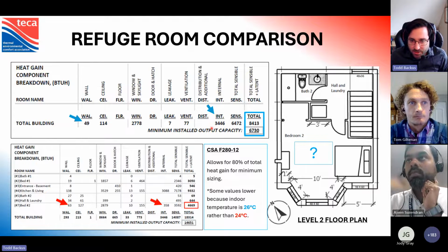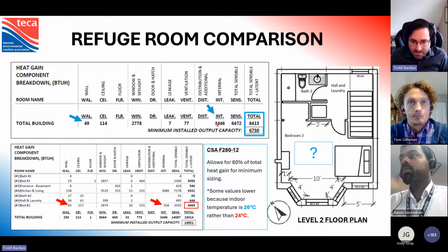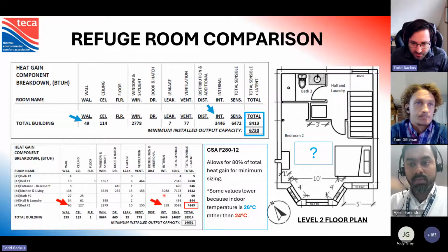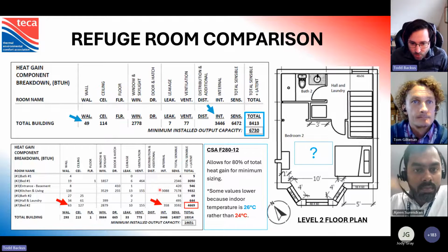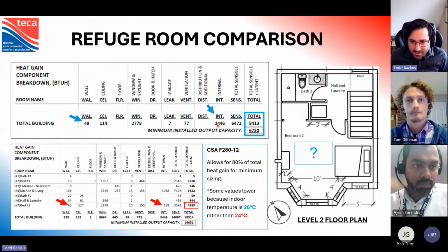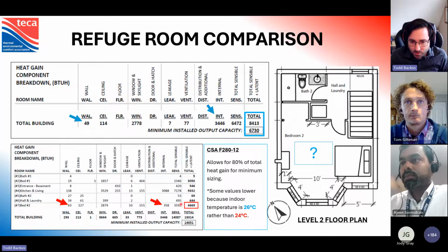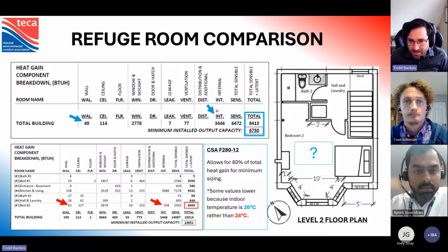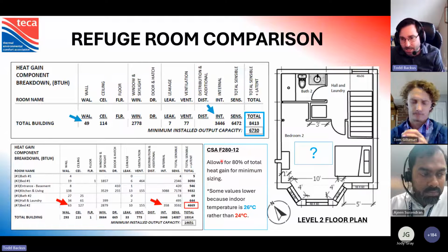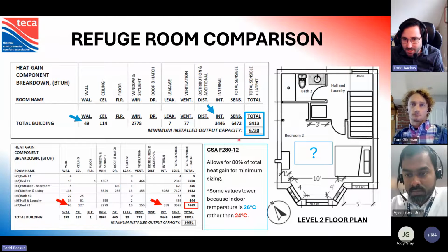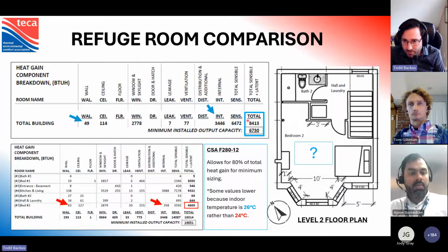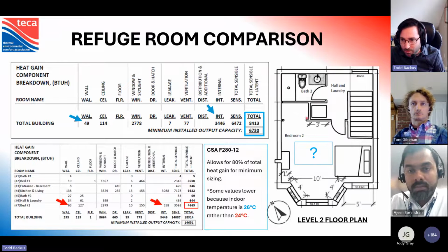These internal loads, which are the electrical and the occupant load, I've made sure show up in this bedroom. Whereas in this inaccurate model, it's been shifted into the kitchen and living room, which is very normal for a whole house. But to then ignore that number and just select this, that's basically the difference, is that you've shifted this internal load into a room that you are ignoring. So I would highly recommend that you don't do that when modeling this accurately. And again, be aware, you only have to meet 80% of the heat gain for minimum sizing according to CSA. I would personally still use the total number, but basically what I'm getting at here is this is a 3/4 ton system. This is a 1/2 ton system. So this does actually matter when it comes to properly sizing this system.